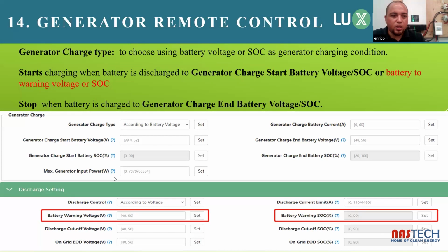Here's more generator settings. Also, discharge settings for your batteries. Your battery warning SOC. So the generator charge type, you can choose either voltage or SOC as the generator charging condition. The generator starts battery voltage or SOC charge according to the battery start voltage. So you would input it here. If you're using lead acid, you will make use of the voltage. If you're using BMS, you would make use of the SOC. And then here as well, you can set your max generator input power.